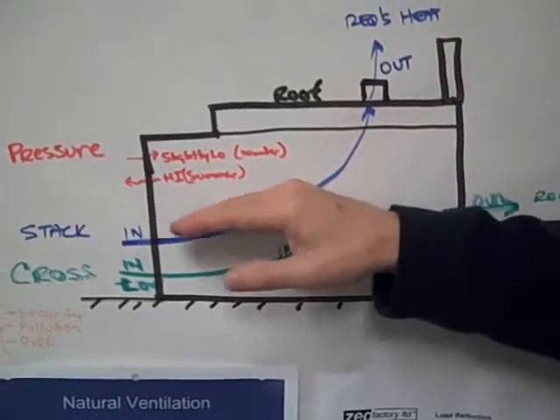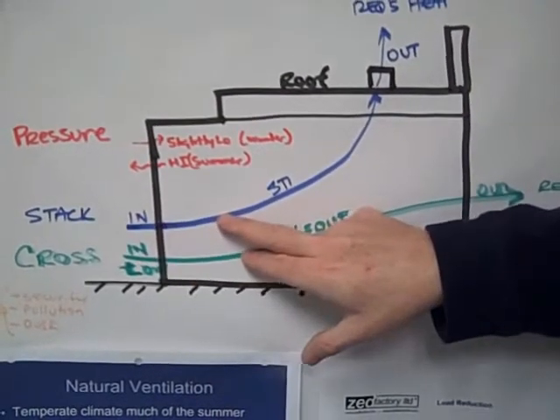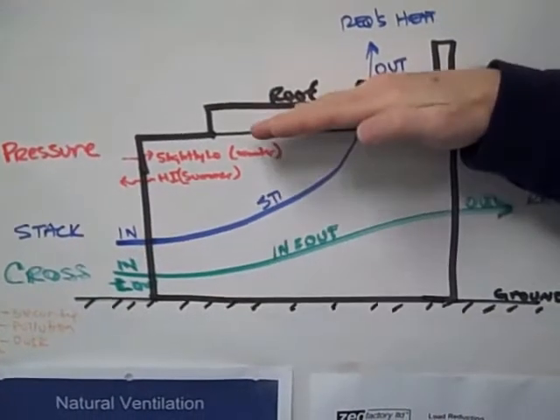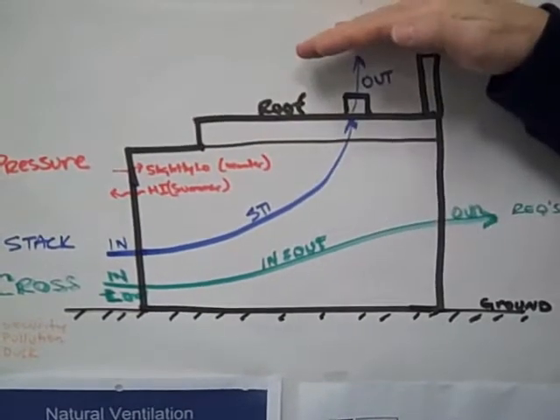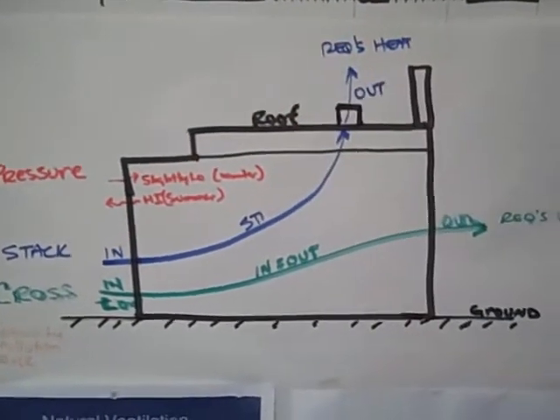The second type is the stack ventilation where you have the inlet low in the front, but then it exits high and it depends on the heat to actually, hot air rises and it goes out the top of the building. And there in the roof, you need some openings to allow it to exit.